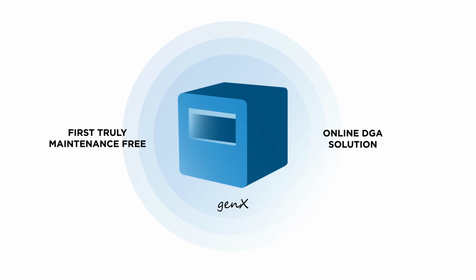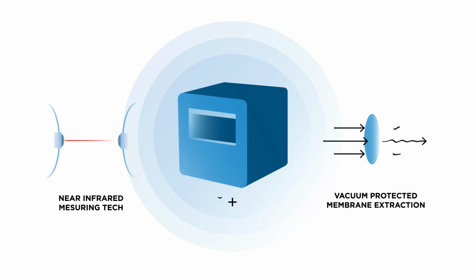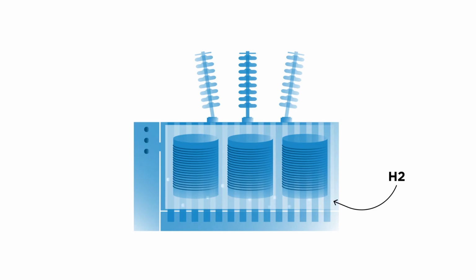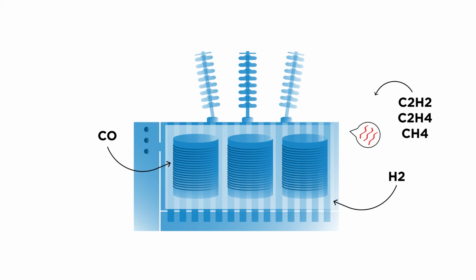The new HYDROCAL genX product family is the first truly maintenance-free multi-gas online DGA solution, combining proven near-infrared measuring technology with vacuum-protected membrane extraction. As hydrogen is involved in nearly every fault of the insulation system of power transformers, and carbon monoxide is a sign of the involvement of the cellulose or paper insulation, the presence and increase of acetylene, ethylene and methane further classifies the nature of the fault as overheating, discharge, partial discharge or high energy arcing.